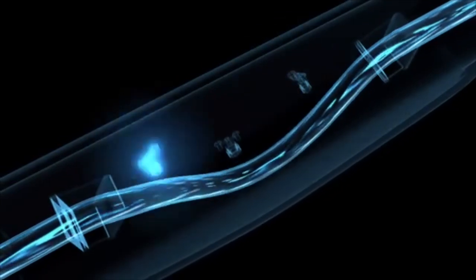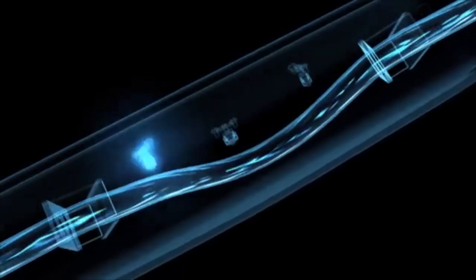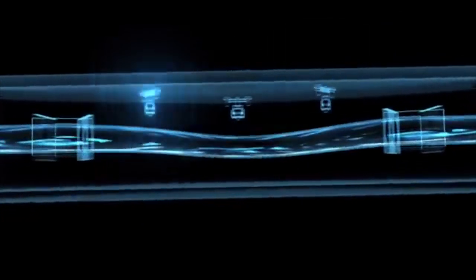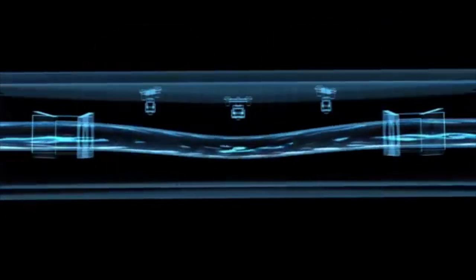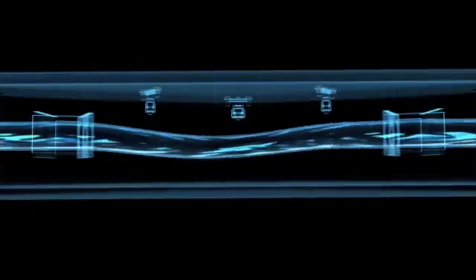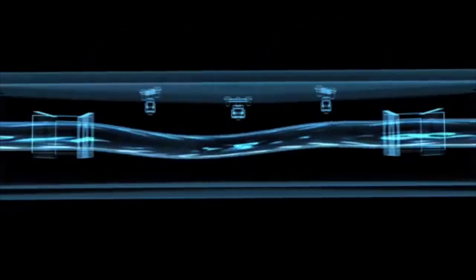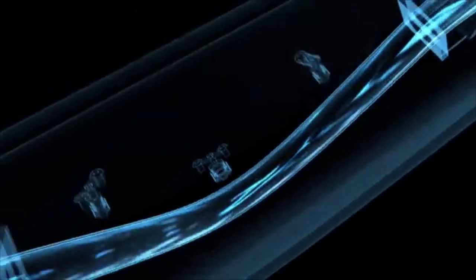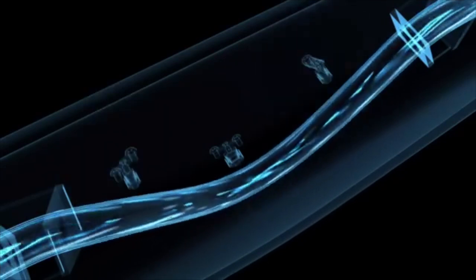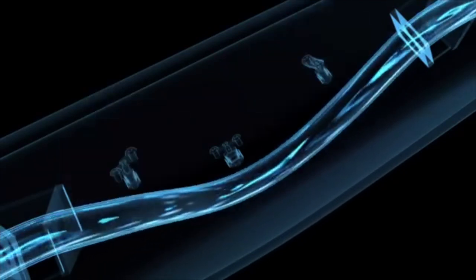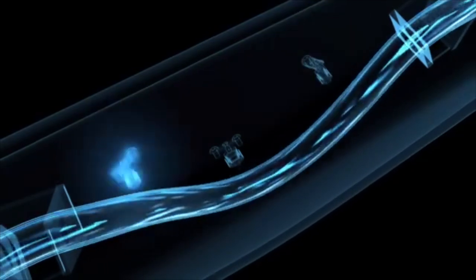As soon as the fluid starts to flow in the measuring tube, however, additional twisting is imposed on the oscillation as a result of the liquid's inertia. Now, due to the Coriolis effect, the inlet and outlet sections of the tube oscillate at a different phase at the same time. The highly sensitive sensors pick up the change in the tube oscillation in terms of time and space. This is known as phase shift and is a direct measure of how much liquid or gas is currently flowing through the pipe.